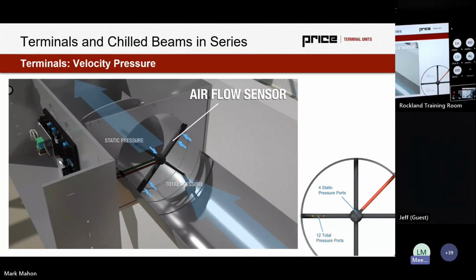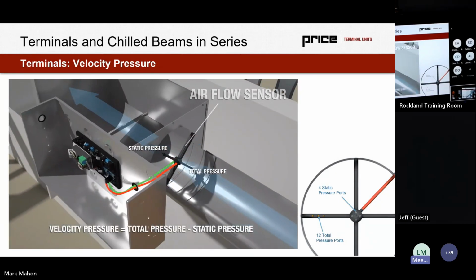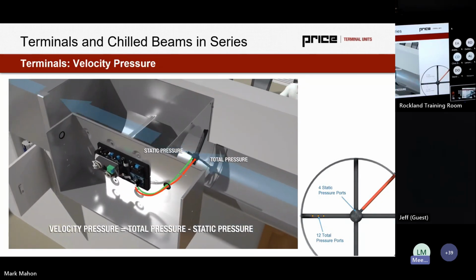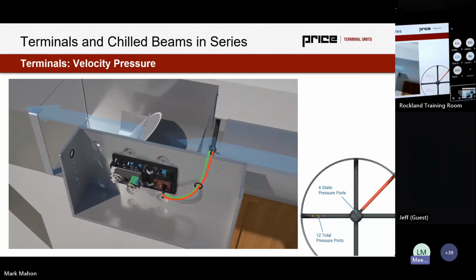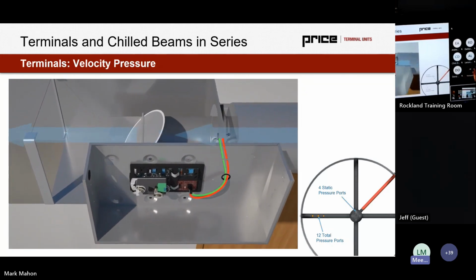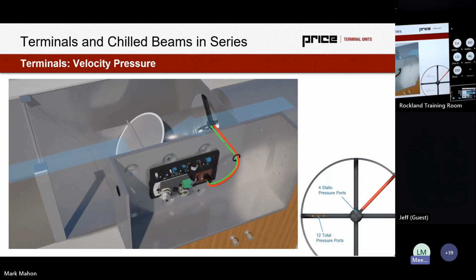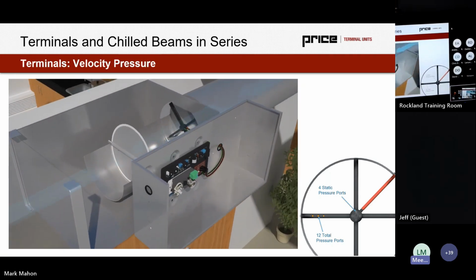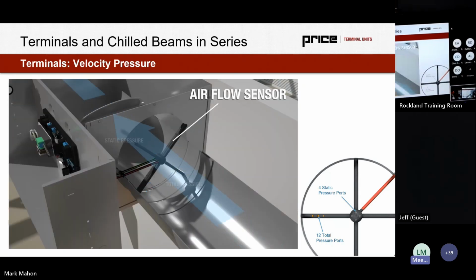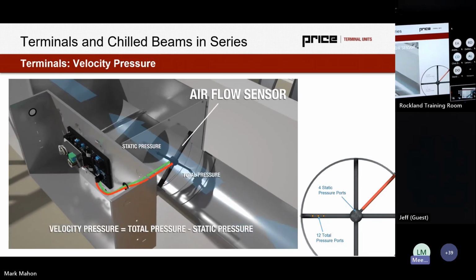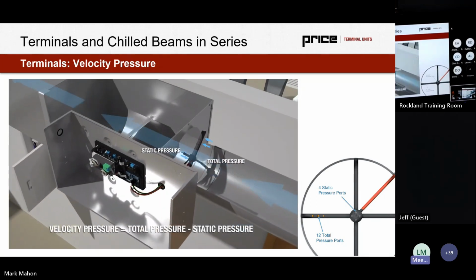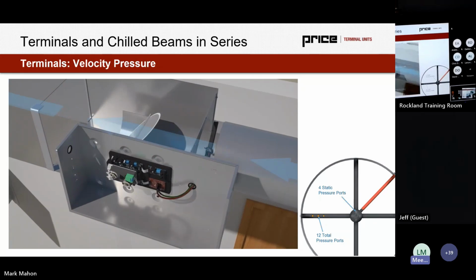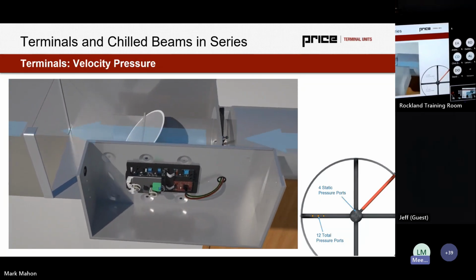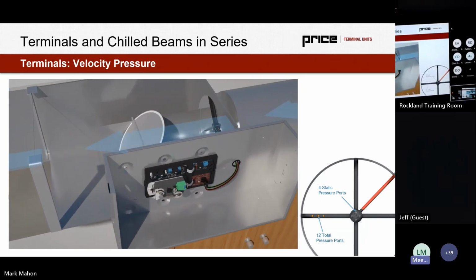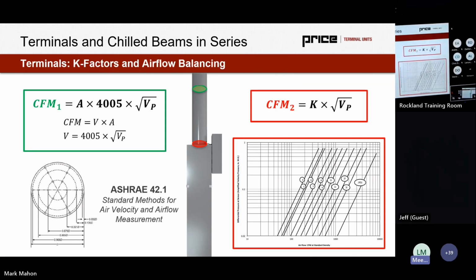It's measuring static pressure only from some ports that are very intelligently hidden on the back of the SP300 sensor. I say that both because I am a fan of Price, but also it was way before my time. So whoever came up with the SP300 sensor is no longer at Price because it was developed a long time ago. But they hide those static pressure ports in a very precarious position. That really means you can never get any kind of velocity pressure influence from it at all, which makes for a really robust signal. And we take the difference of those, and that's actually how we measure and control for airflow.